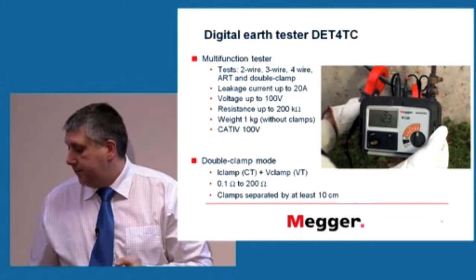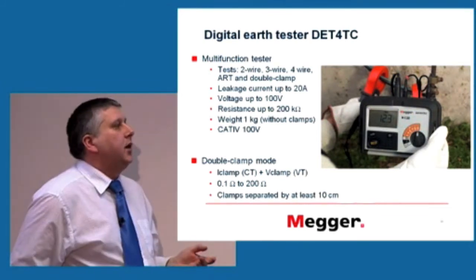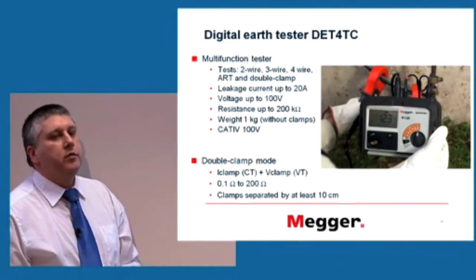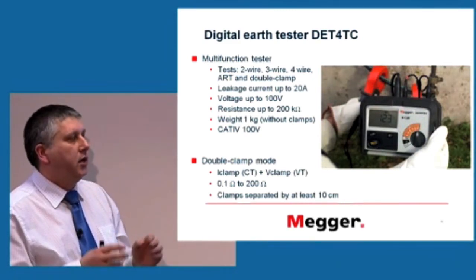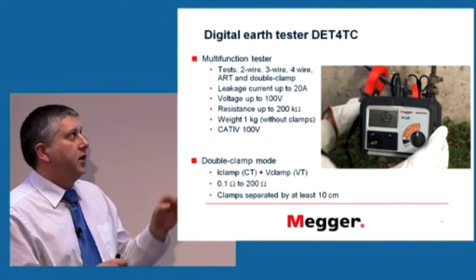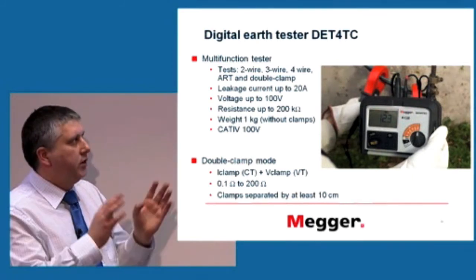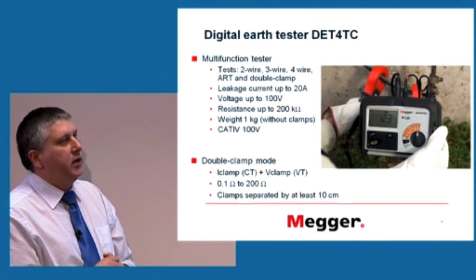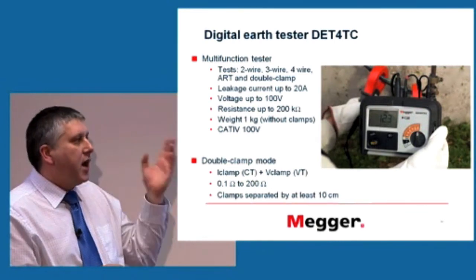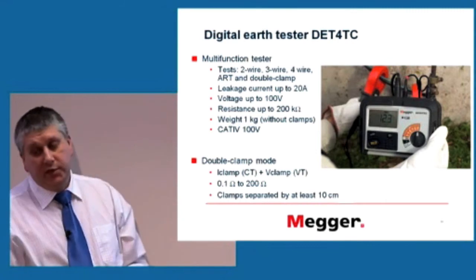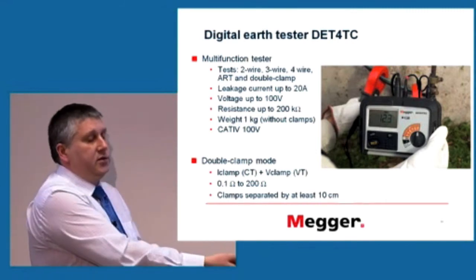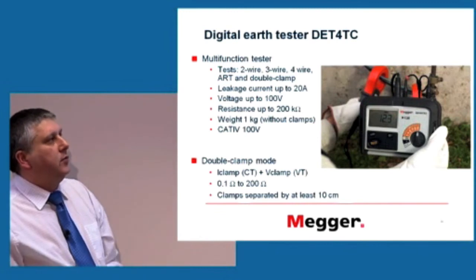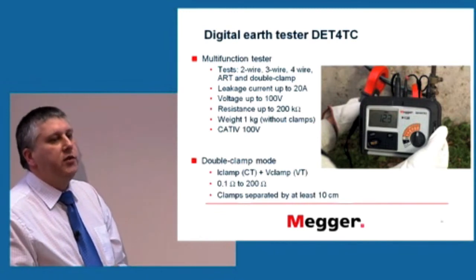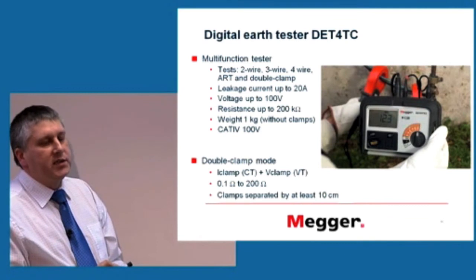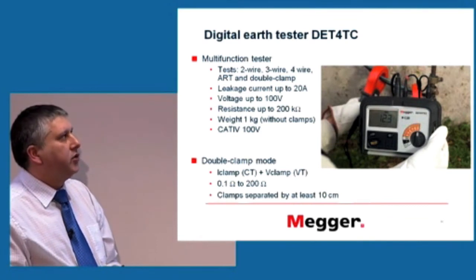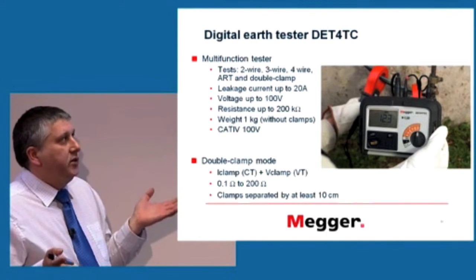This particular tester is a multifunction tester. It can perform any other measurement in terms of measuring earth resistance. It can measure 2-wire, 3-wire, 4-wire, all the regular ways of measuring resistance of the earth. It can measure current. So if there's any current flowing in that electrode, because we have a current transformer, just clamp around it and see what that current is. And this value is only 20 amps because there's no need for more. You wouldn't expect a very high leakage current in that electrode. It can measure just voltage. It's a voltmeter as well.